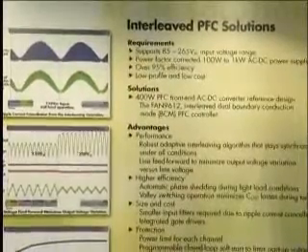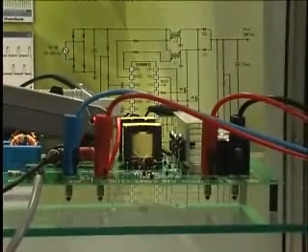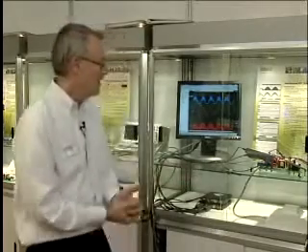For high efficiency, one example is what we call valley switching. We take advantage of the natural resonance that occurs before the turn-on of the main switches in the powertrain, and we look at the slope of the drain-to-source voltage and turn it on right when that voltage is at a minimum. That reduces our switching losses considerably. Another efficiency improvement is that at light load, we turn off one of the two channels, eliminating switching losses and boosting our light load efficiency.